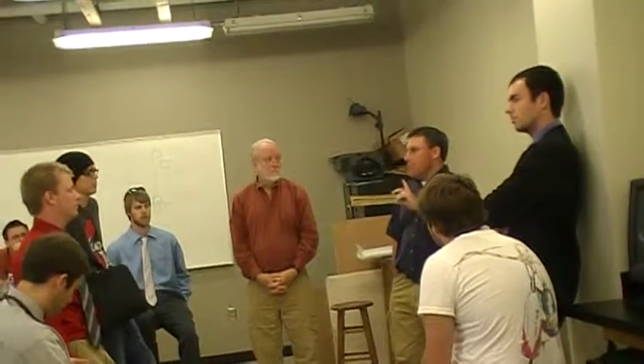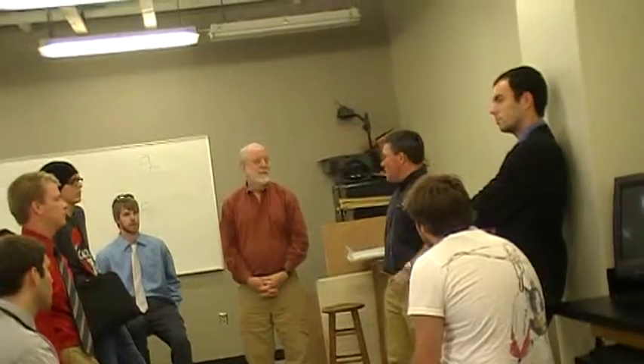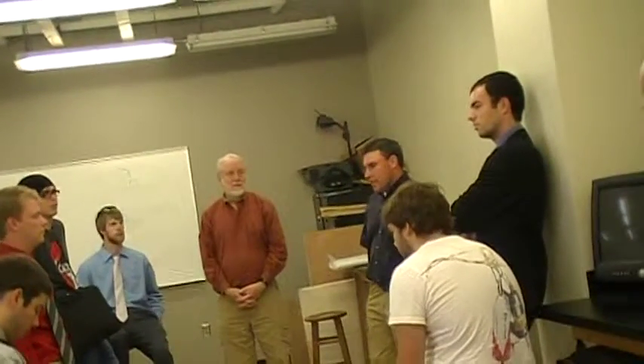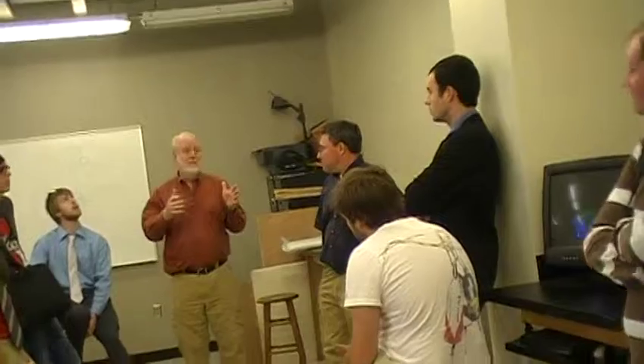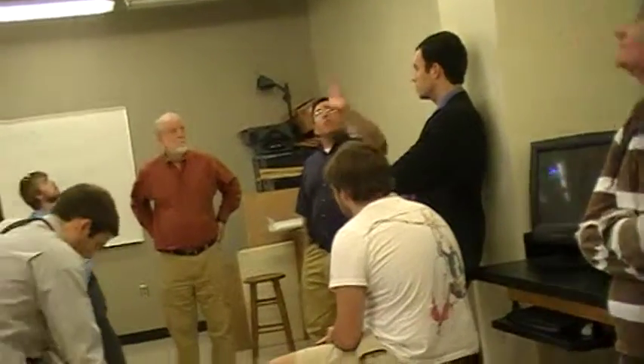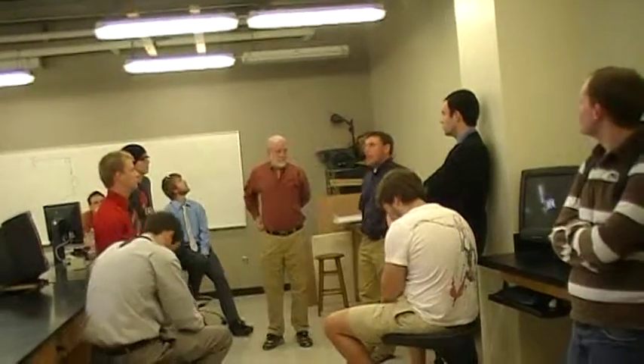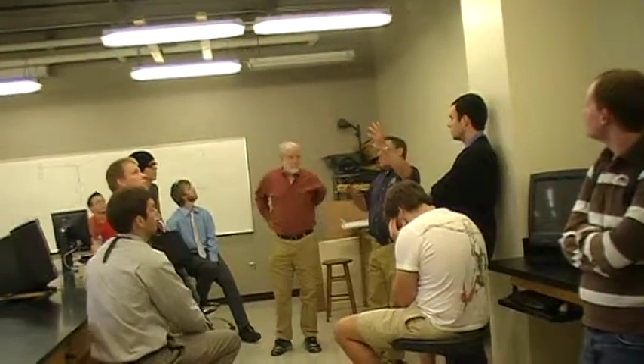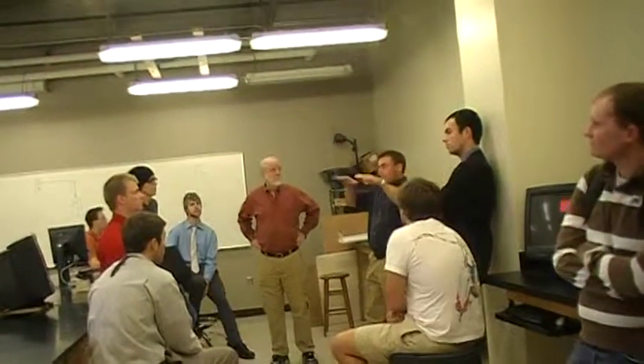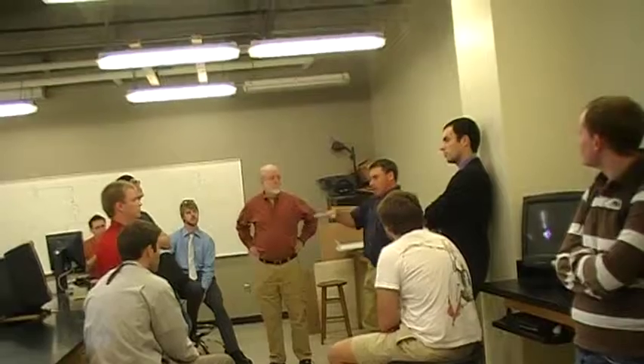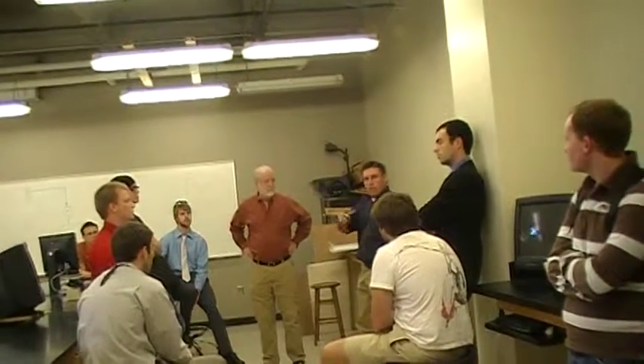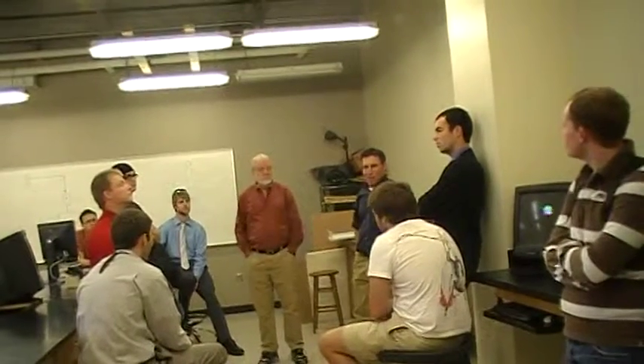That comes down from the system office, the engineer with the UT system office, his standard is 1 thermostat per 3 offices. Yours may be a little bit over that, but typically it's 3. But it could be 5, just depending on how the system's set up. You could put a VAV box in each individual room, but to cut down, basically what you'll have is a VAV box. Unlike this being a classroom, if this was 3 offices, you would have this VAV box serving this office, and that office on either side. But one person in the middle, whoever's got the thermostat has control.